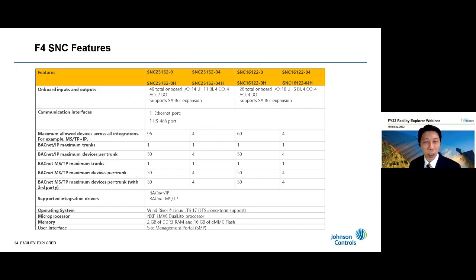We have also provided a smaller size for a plant room application, like the middle size, with 4 devices support. For example, you can connect an SNC with some I/O expansion together with some equipment controllers, a few equipment controllers - let's say for pump, some for cooling tower - and maybe with central logic in the SNC to make these different plant room and system equipment work together, supervised by a single plant controller.